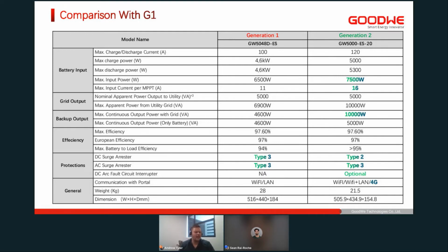And one other thing just to highlight, I think, especially when it comes to residential installations, the lighter and the smaller the inverter, the better, I guess. You've normally got very tight spaces to fit these devices in, and also it makes it easier for one or two guys to install the device on site. The new device is around 6.5 kgs lighter, and in terms of dimensions, it's quite a bit flatter, or it has less height, I guess.